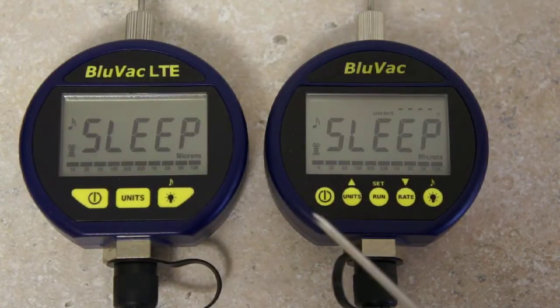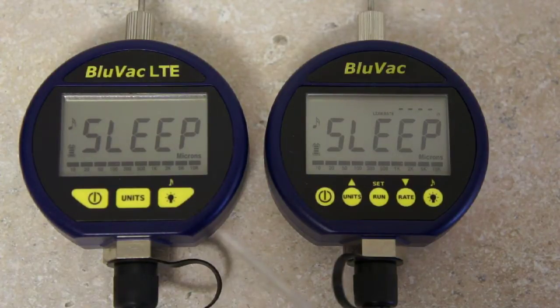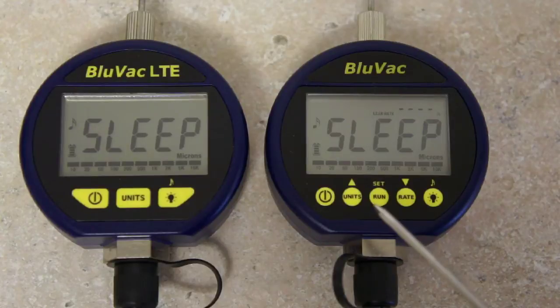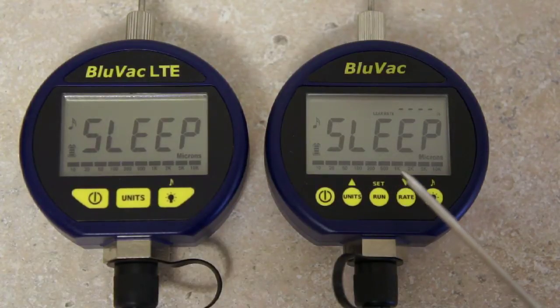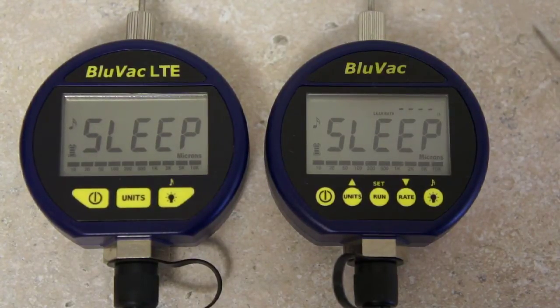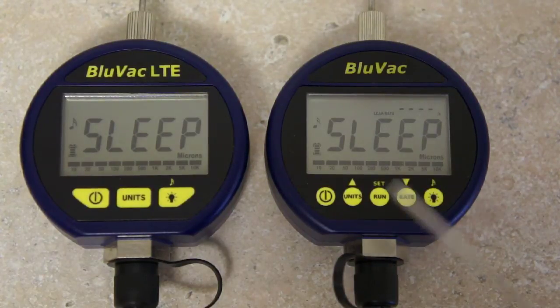I've got the two BlueVacs sitting side by side and you can see they look essentially the same aside from the buttons. They're pretty much identical as far as sensor technology and display go. It's just productivity features that are in the BluVac that aren't in the BluVac LTE — things like the ability to program the gauge to alarm at a set vacuum level so you can come over and do your decay test. The BluVac original also has a tenth of a micron resolution and a leak rate indicator.